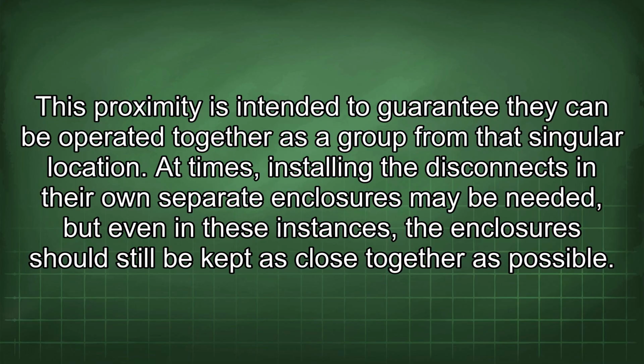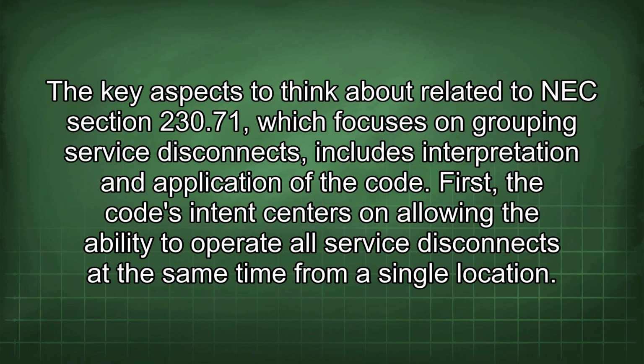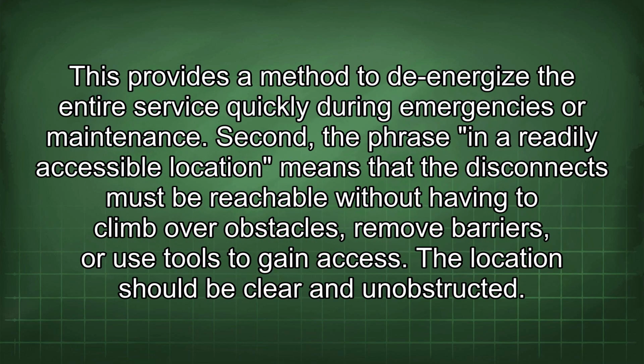At times, installing the disconnects in their own separate enclosures may be needed, but even in these instances, the enclosures should still be kept as close together as possible. The key aspects to think about related to NEC Section 230.71, which focuses on grouping service disconnects, include interpretation and application of the code. First, the code's intent centers on allowing the ability to operate all service disconnects at the same time from a single location. This provides a method to de-energize the entire service quickly during emergencies or maintenance.